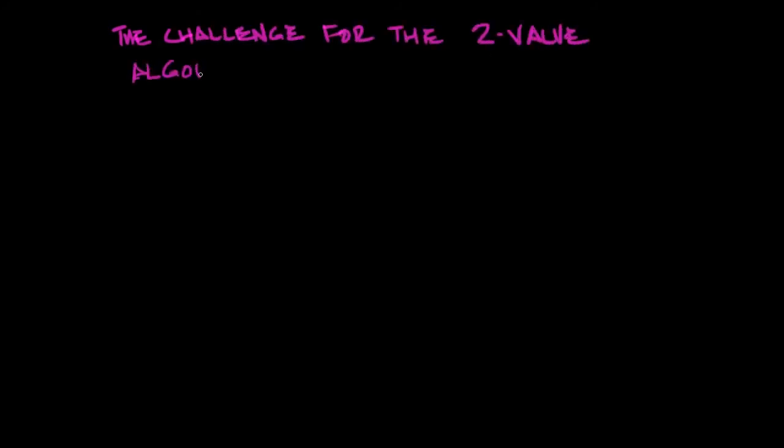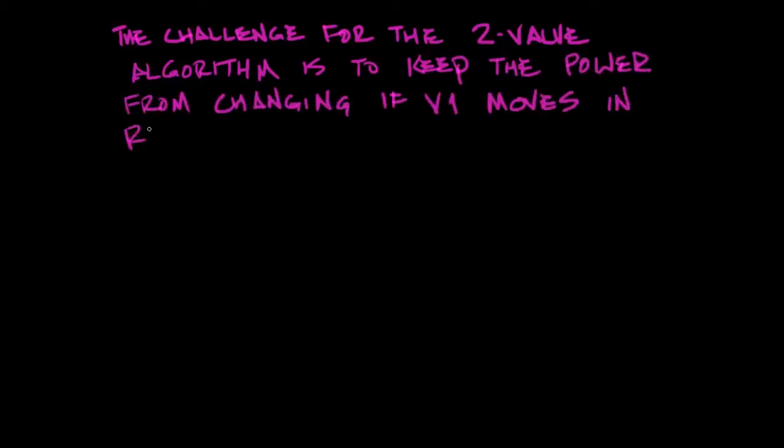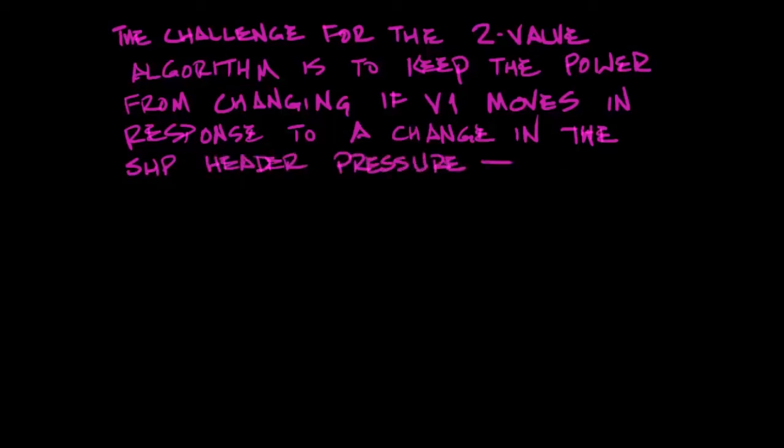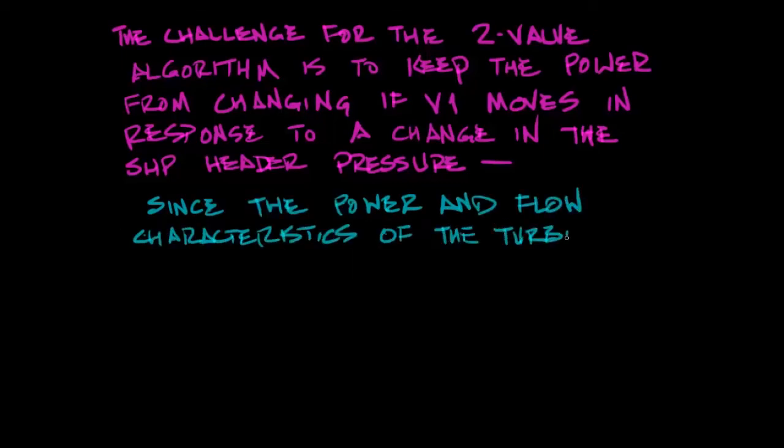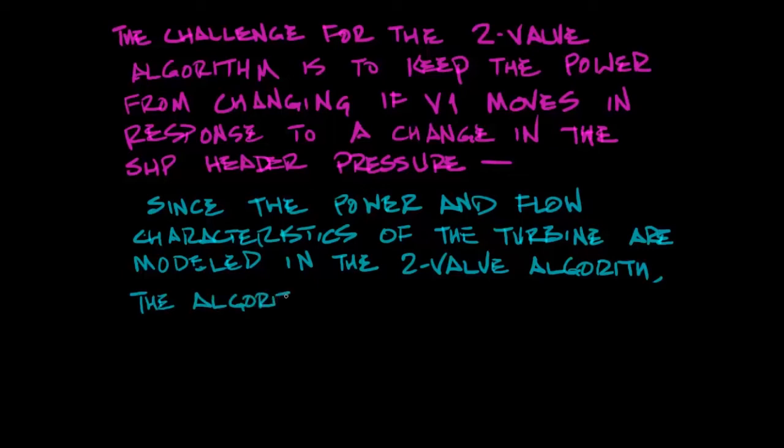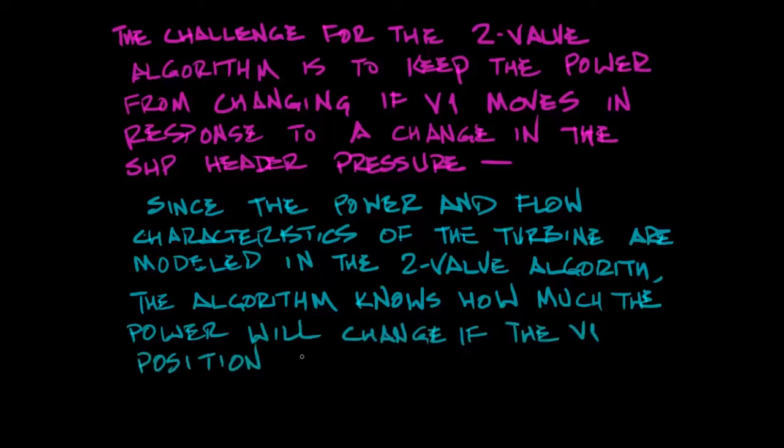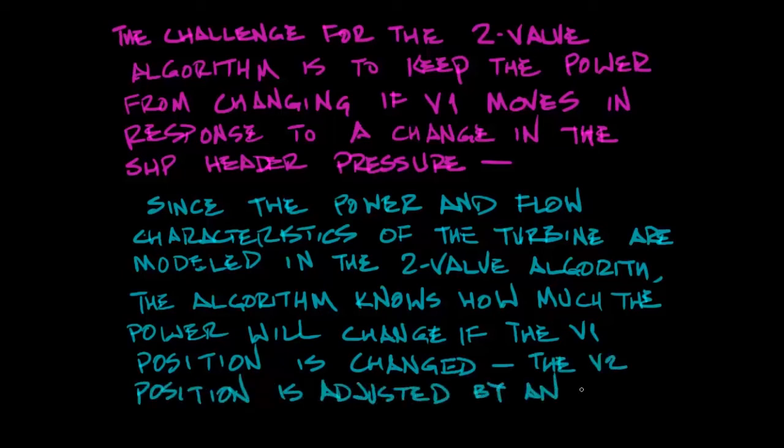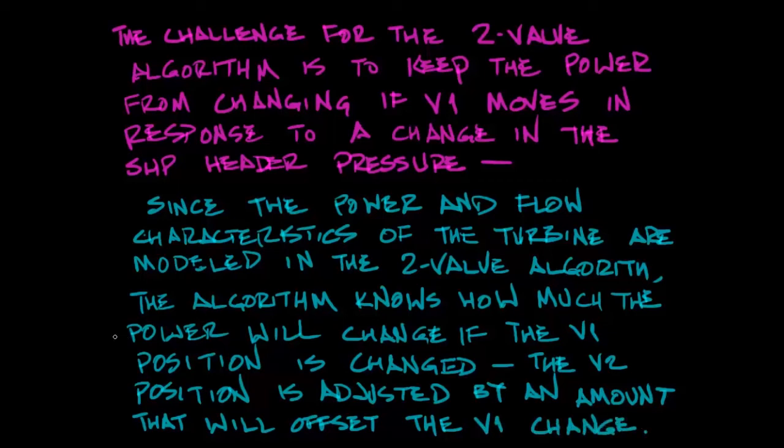The challenge for the two valve algorithm is going to be keeping the power from changing if V1 moves. If you move V1 in response to a change in the SHP header pressure that's going to change the power produced by the turbine. Since the power and flow characteristics of the turbine are modeled in the two valve algorithm it's going to know just how much the power is going to change based on any change in V1. That means the V2 position can be adjusted by an exact amount that will offset the change that took place at V1.